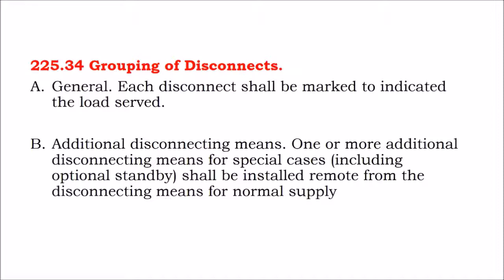As long as you have no more than 6 switches grouped in one location, and it's all related to power supply, you're going to be fine. If you have a standby system where it doesn't really matter if it gets turned off or not, you don't need to worry about it too much either. But if you're designing an emergency backup system where there are critical loads that must remain energized, even when the fire department is trying to purposefully power down the building, those switches need to be separate from the normal power supply to indicate to the fire department that they're there.